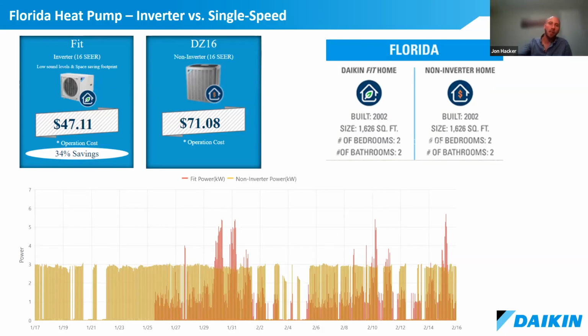For this example, we've taken a 16 SEER, both products are 16 SEER. One has an inverter and one does not, and we've monitored the energy consumption. This is a simple way to demonstrate some of the real world benefits on a pretty big scale in a couple of different climates. This example is in Florida, and it is for a heat pump. Looking at the graphics below, we're going to go through a number of examples of these across the country as we wind down on time.